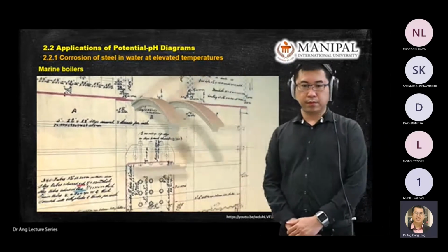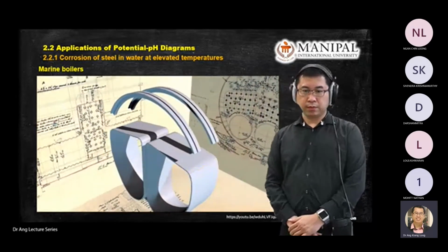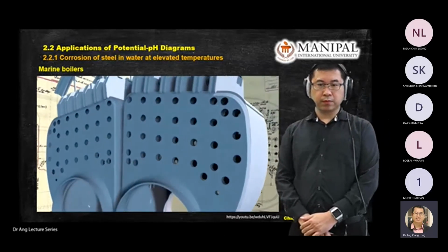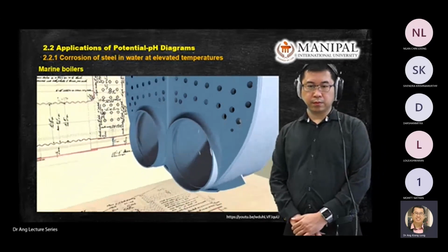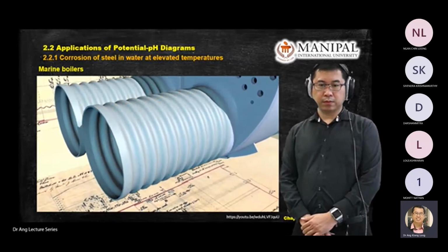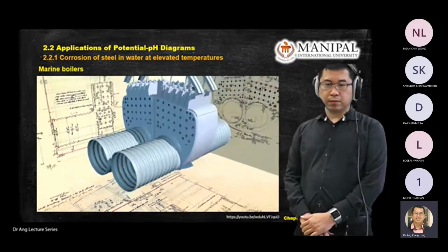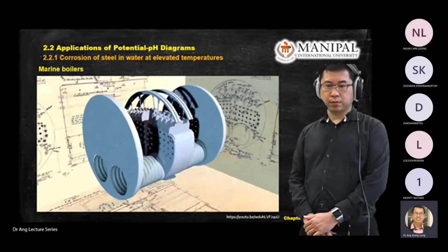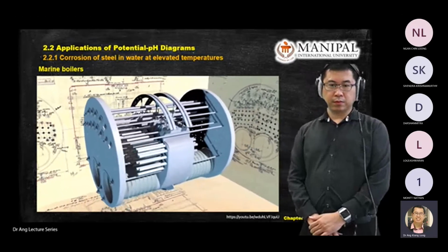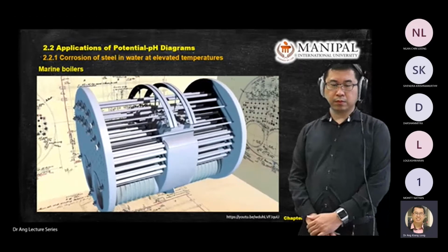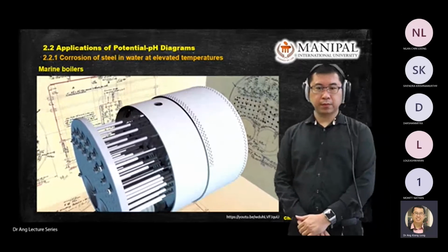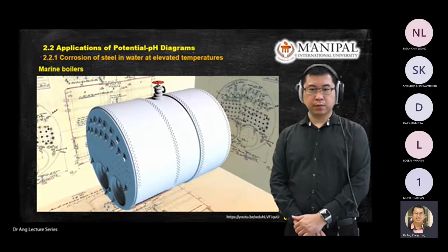We start in the middle of the boiler and see how the centre section, the combustion space, is supported. The two large holes are for the furnace tubes. The smaller holes for the fire tubes. The furnaces are corrugated to give added strength and to increase the area available for heat transfer from the hot gases in the furnace to the water. The outer tube plates are put in place, linked by stay rods and secured by nuts. The fire tubes are now inserted, rolled into place with a tube expander. There was no welding until well into the 20th century. The boiler shell is then riveted in place and a steam valve located on top to distribute steam.